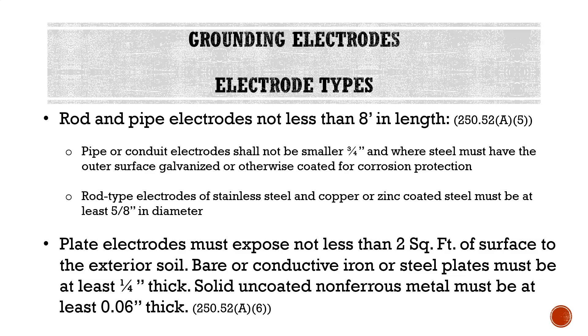Plate electrodes must expose not less than 2 square feet of surface to the exterior soil. Bare or conductive iron or steel plates must be at least 1/4 inch thick. Solid, uncoated, non-ferrous metal must be at least 0.06 inches thick. Once again, these requirements pertain to plate electrodes.